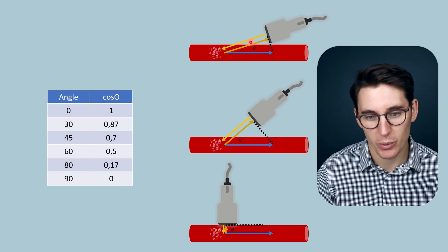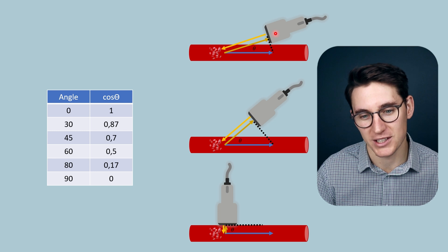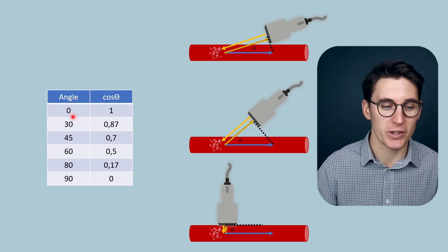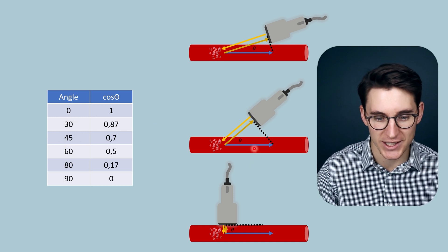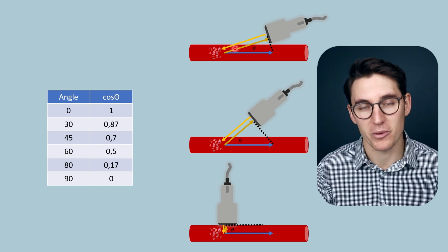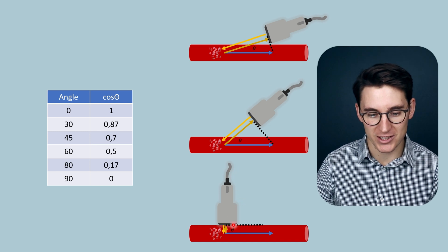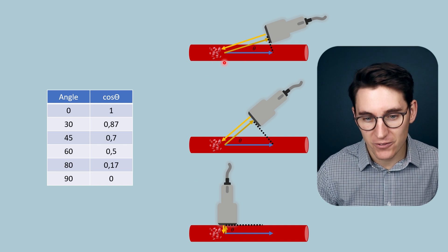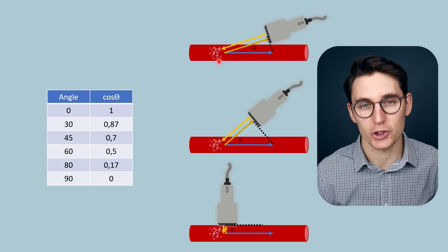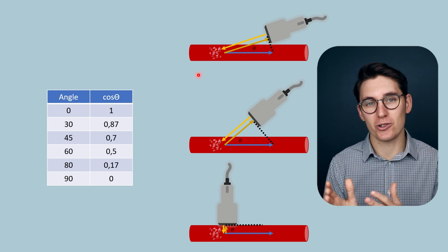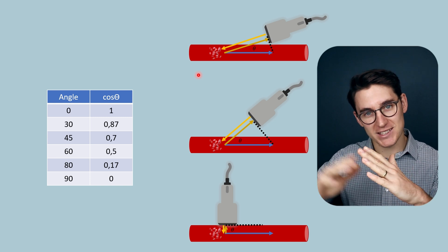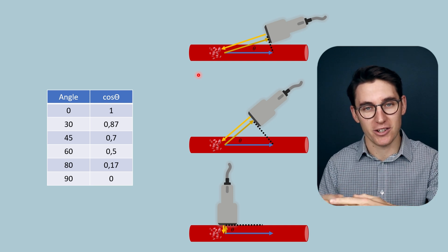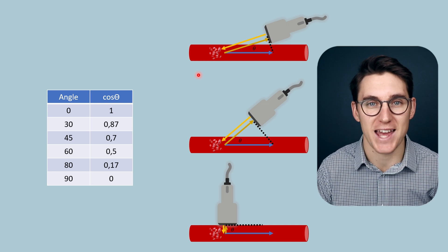At very steep angles we run into refraction problems, as the ultrasound wave must travel through the blood vessel wall. Generally we prefer an angle between 30 and 60 degrees to get an accurate calculation without refraction problems. This compensation for the angle of incidence using the cosine theta value is what's known as angle correction — the Doppler shift calculated at a certain angle is accounted for so that velocity can be accurately calculated.